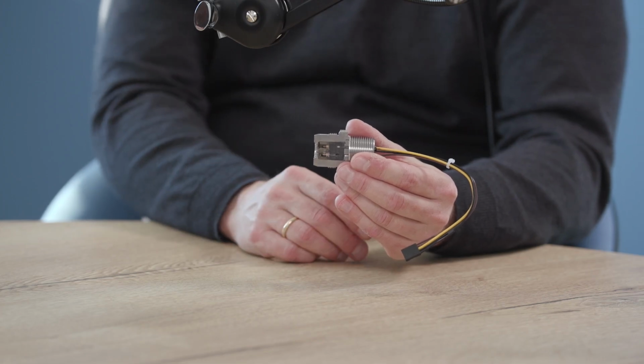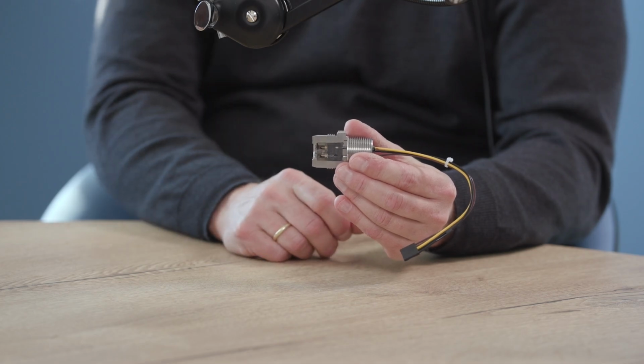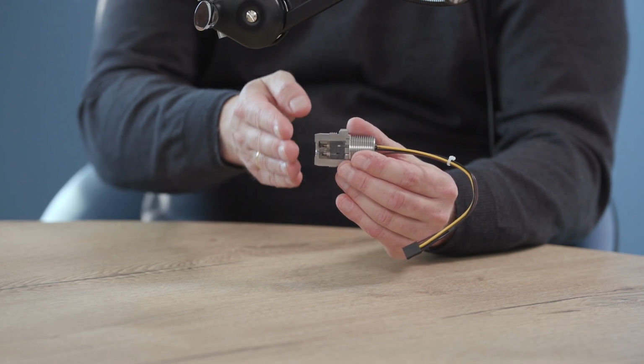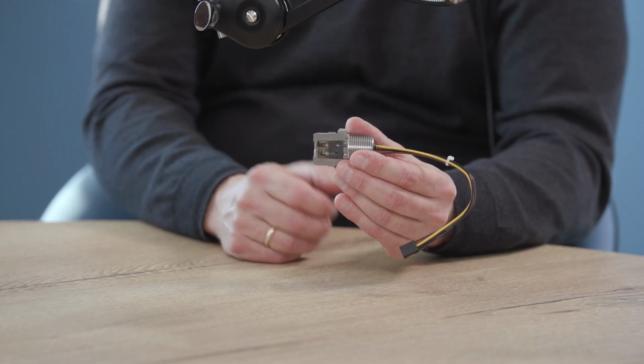If you have a designed sensor which is, like we described at the beginning, active-passive pearl, then you are limited in this direction. Because if you would mount it horizontally, then you would have a problem. You have a kind of chimney effect inside, because depending on where the hot pearl is, you will have a cooling effect with the airstream going by. So the heater will always be active and creates a kind of reading which is not present, like a false zero or a drift, maybe? Yeah, correct. Okay. And if you have, like our design, with separation, then it doesn't matter. The only thing you shouldn't do is point it up, because then the probability is quite high that the entry will be blocked.